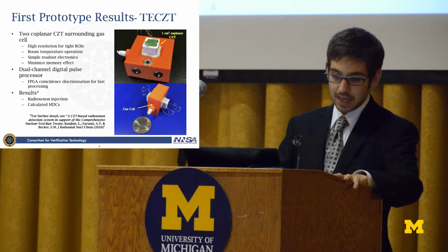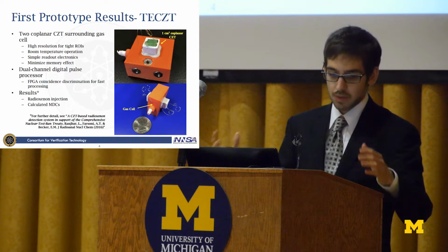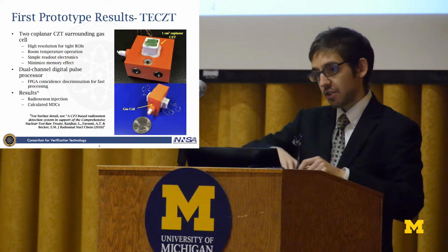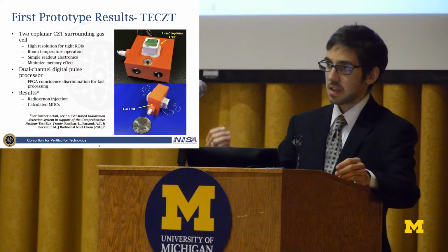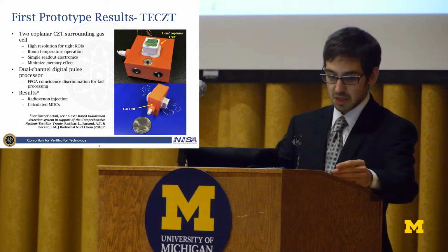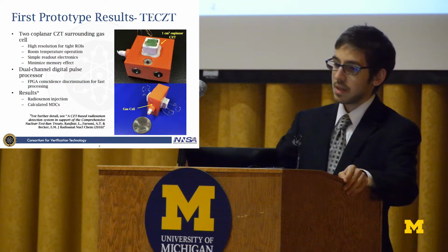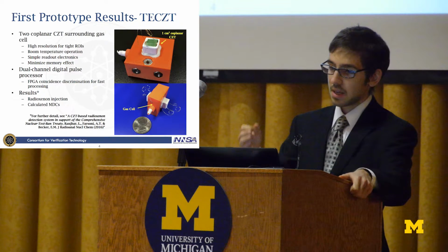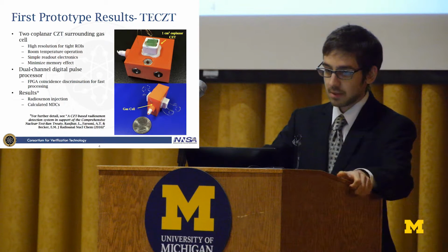Now, memory effect is when you have the diffusion of xenon into the surrounding material. And these xenons, after you flush out the gas cell, the xenon will stay in the material that it's diffused into and decay. And this causes worse MDCs. Now, this doesn't happen as much with solid-state detectors as it does with, say, plastics. And so we used this in order to avoid memory effect as much as possible.